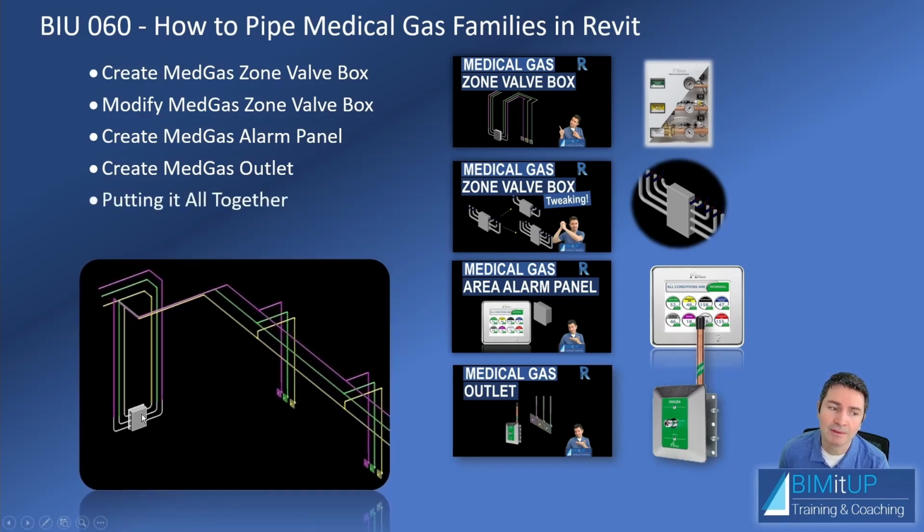So we're going to have the medical gas zone valve box, we're going to pipe to the outlets, and we're going to place the alarm panels that are going to be monitoring those. And then we will tag all those zone valve boxes and alarm panels. And then at the end, we're going to create a smart schedule that is going to display all the information contained in all those medical gas devices.